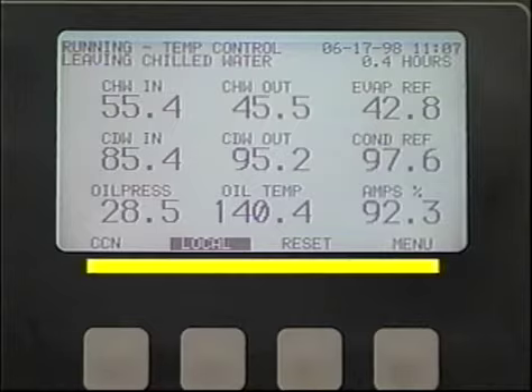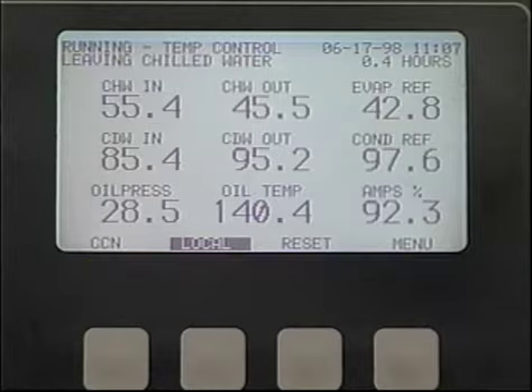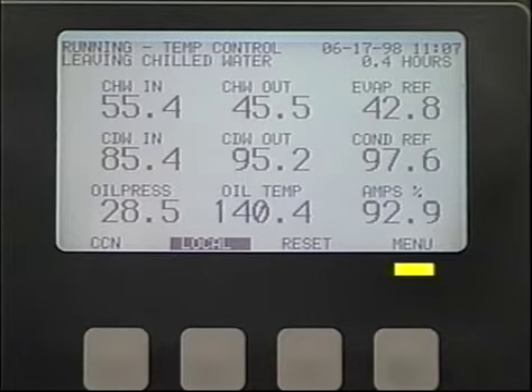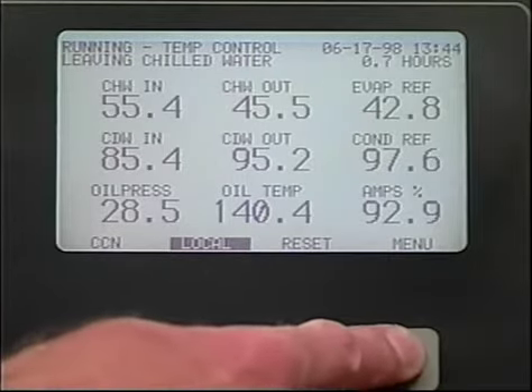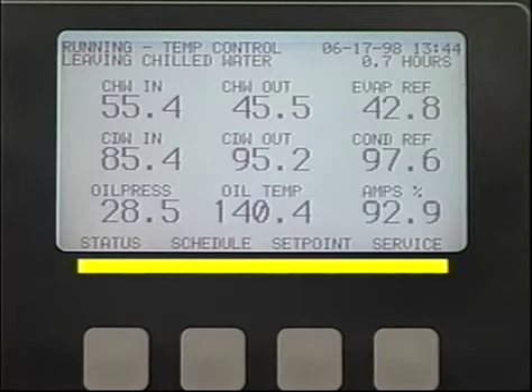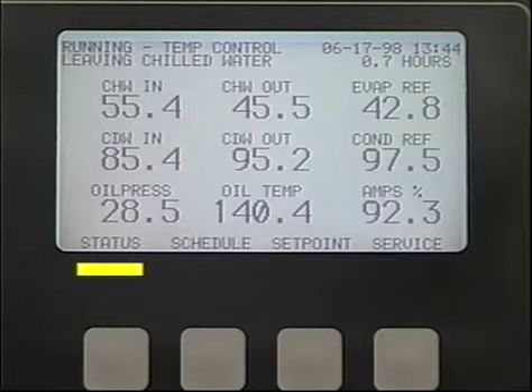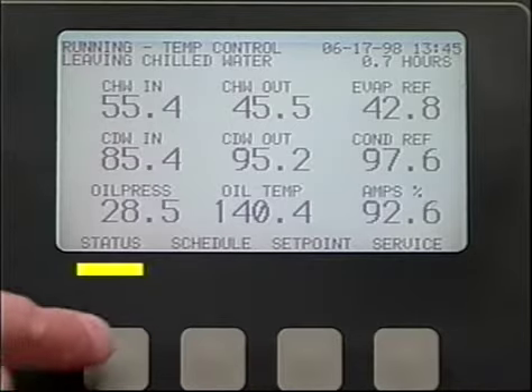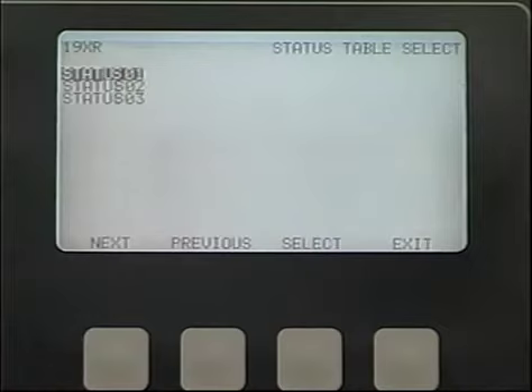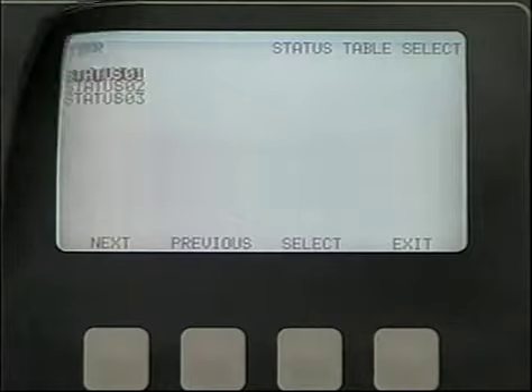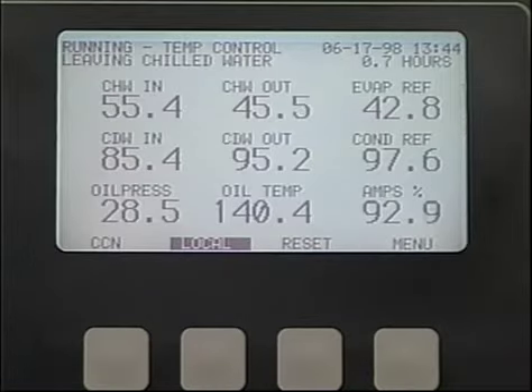The function of the keys below the display is identified in the bottom line of the display. When the default screen is displayed, the last key at the right is called Menu, and depressing it reassigns the function of all 4 keys. They now become Status, Schedule, Setpoint, and Service, which are the 4 major divisions of the software. Depressing the status key allows you to select any one of 3 screens that contain additional operational data. Of course, while you're doing this, the default screen disappears, but it will return again as soon as the lid keys have been idle for 5 minutes.